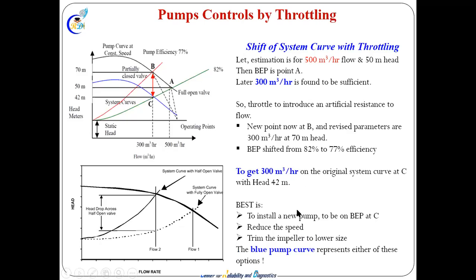At 300 you can see here you have to encounter 42 meter head. Here it is 82%, the 77% efficiency point, and at 70 meter head, and here it is 42 meter head.